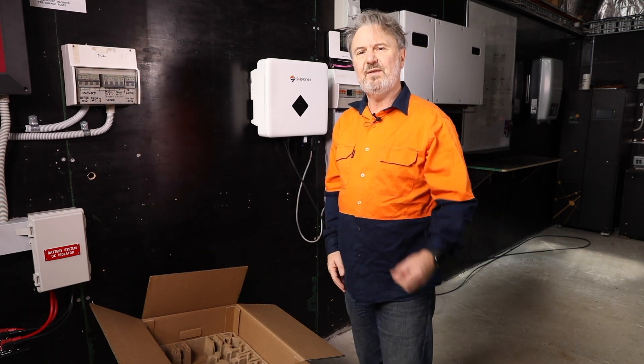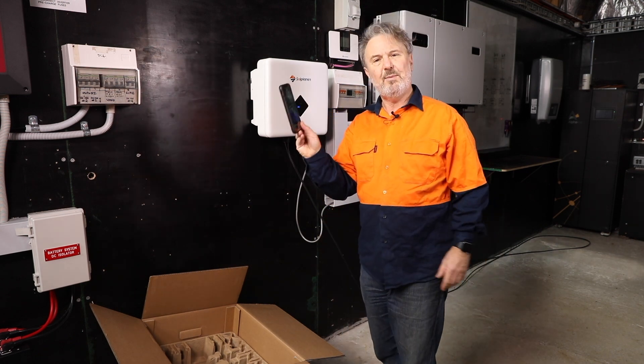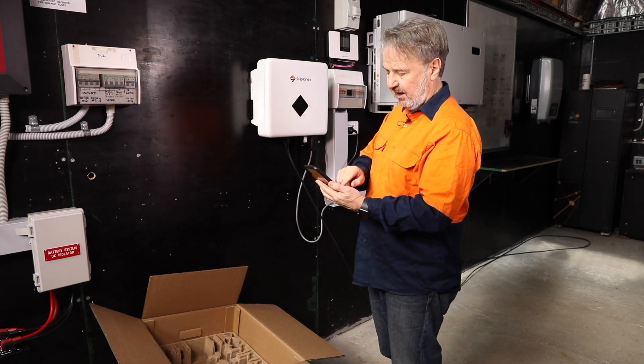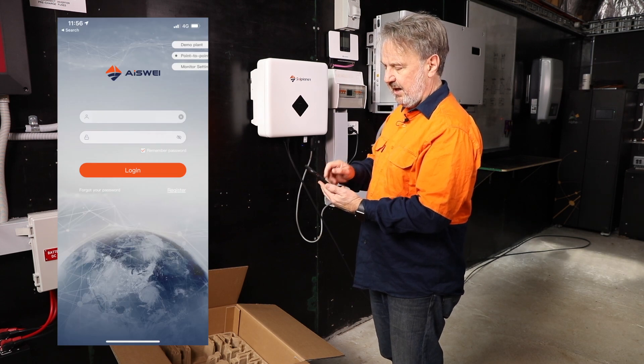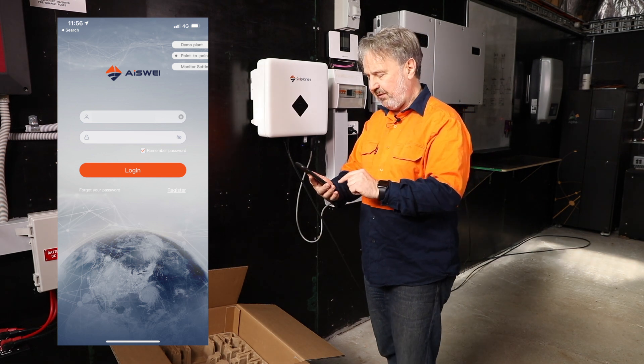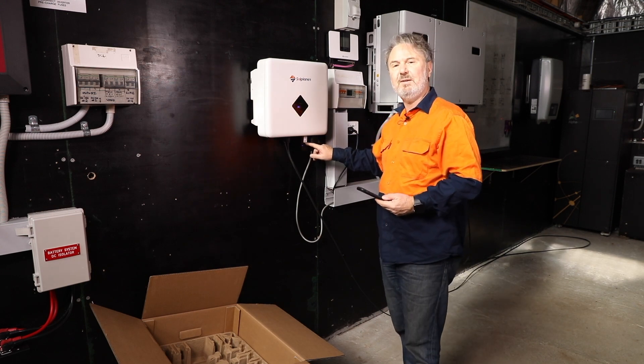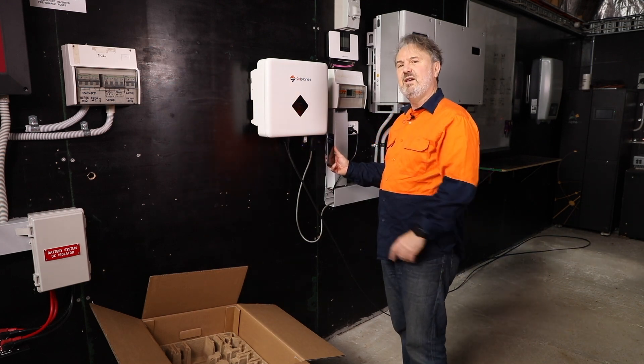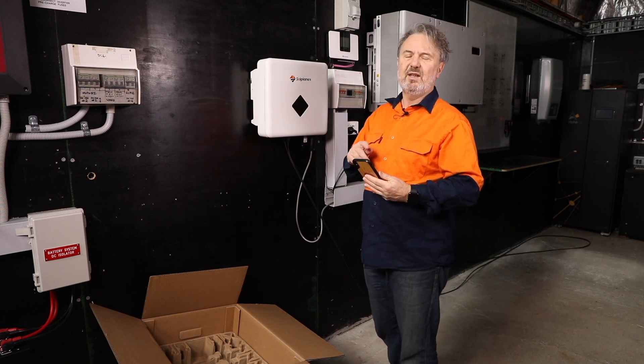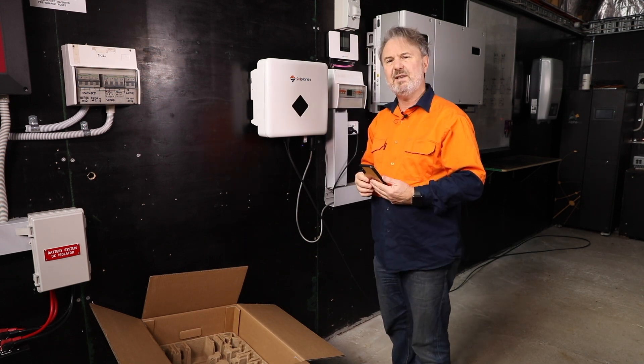The next step when installing an inverter is setting up the grid parameters. Like many inverters these days, it's done with an app — the app for the SolPlanet is the AiSwei app. I launched the AiSwei app; I won't run through the whole process, but effectively it's a matter of connecting to this unit. There's a QR code right on the front, and pointing the app at the QR code will read it and get the serial number automatically. You can then start putting in the grid parameters.